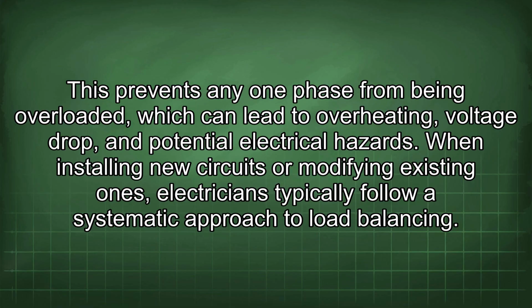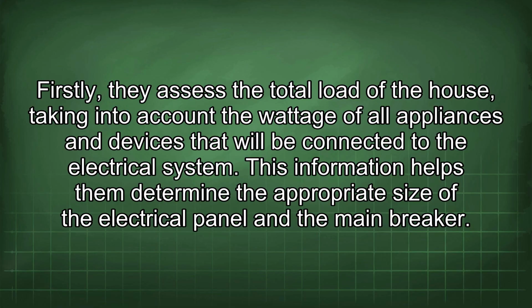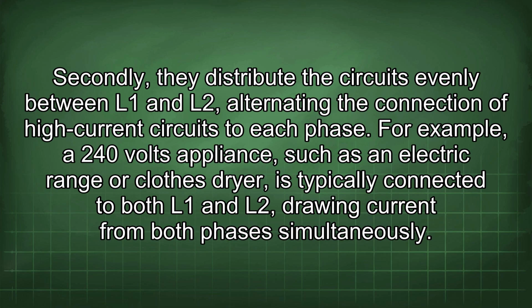When installing new circuits or modifying existing ones, electricians typically follow a systematic approach to load balancing. Firstly, they assess the total load of the house, taking into account the wattage of all appliances and devices that will be connected to the electrical system. This information helps them determine the appropriate size of the electrical panel and the main breaker. Secondly, they distribute the circuits evenly between L1 and L2, alternating the connection of high current circuits to each phase. For example, a 240-volt appliance, such as an electric range or clothes dryer, is typically connected to both L1 and L2, drawing current from both phases simultaneously.